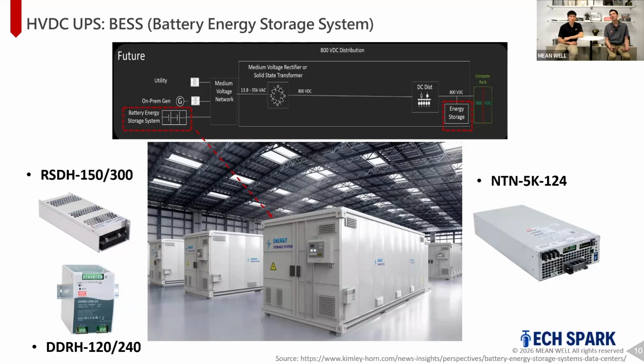But for data centers, 800 volt is typically the voltage that's required. So with energy storage, you see on the input side, the primary side, and also there's a small one on the output side. Those two have their own function. The one on the AC side, the primary side, installed right next to the generator, is to back up the generator, so when AC goes out, it kicks in for the generator to start up. Those are 800 volt.